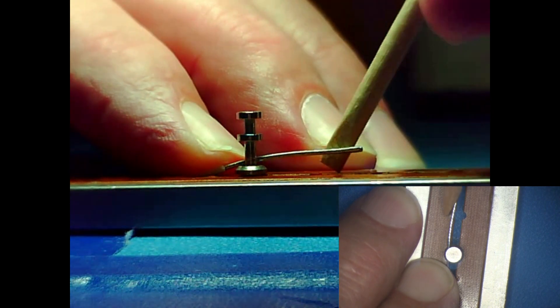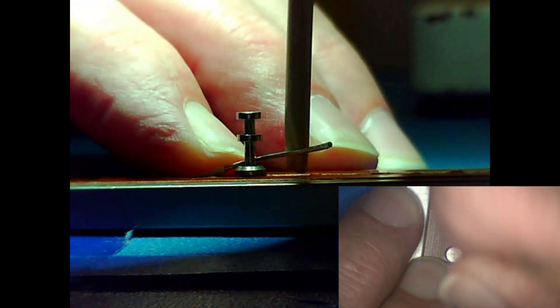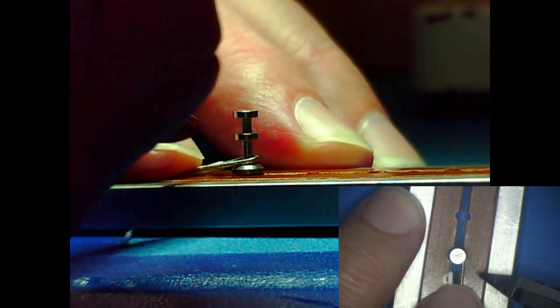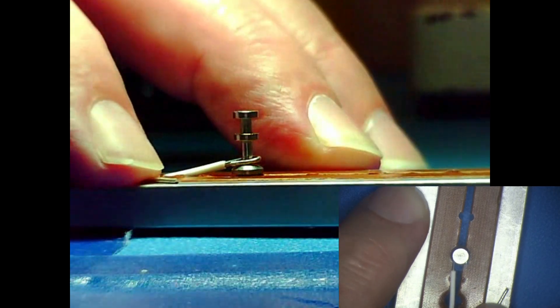Wrap the tinned wire directly to the terminal. Use a wooden stick or other tool that will not damage the wire, terminal, or the assembly. Trim the end of the wire approximately even with the outer edge of the base of the terminal.